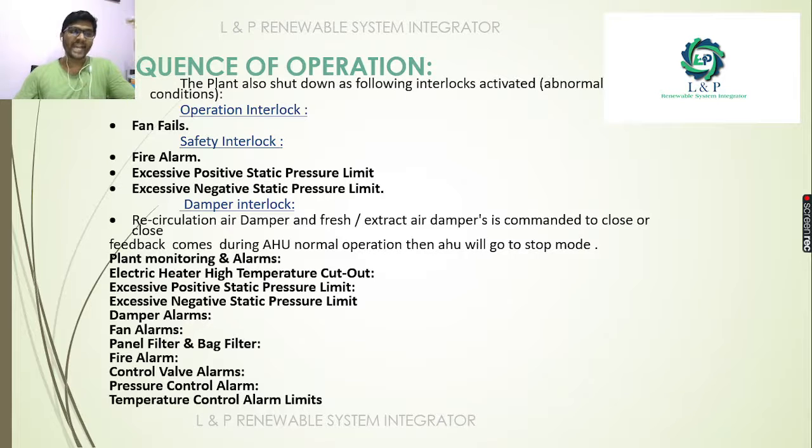We can also have alarms for the control valve if we are giving some command. If for the given command the control valve is not operating, we can create an alarm. We can give a time delay for how long the control valve will take to operate. If it is not operating in that particular time, you can raise the alarm. Even for the temperatures also.